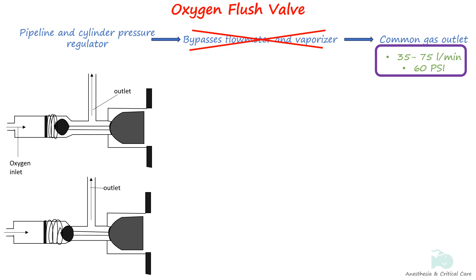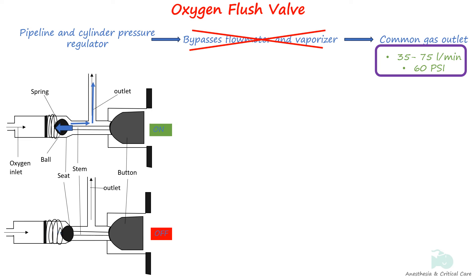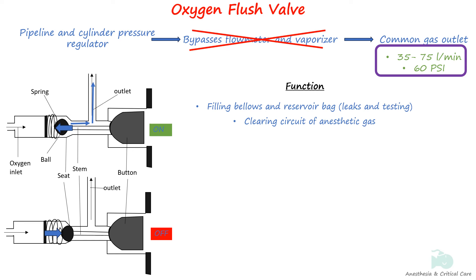The oxygen flush consists of a button and stem connected to a spring-loaded ball that is in contact with a seat. When the button is pressed, the ball is forced away from the seat, allowing oxygen to flow through the outlet. The spring opposing the ball closes the valve when the button is not depressed. The O2 flush is commonly used to recharge the bellows in case of a leak in the patient circuit, or to rapidly purge the patient circuit of anesthetic gases in the event of an overdose of anesthetic agent.